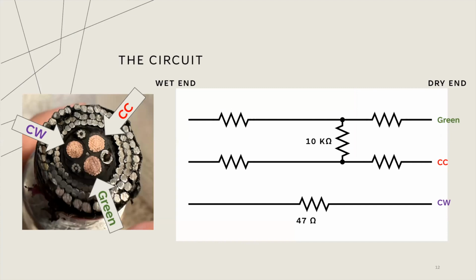So this leads to the test that we used that actually ended up working. This is a very simplified version of our circuit. You have the green conductor, and the conductors counterclockwise and clockwise of it. So the fault was across the green and the counterclockwise conductor. And the resistance of the full conductor was 47 ohms. So using this standard from the data sheet, we can calculate 4.9 ohms per kilometer is 9.6 kilometers for the full length of the cable.